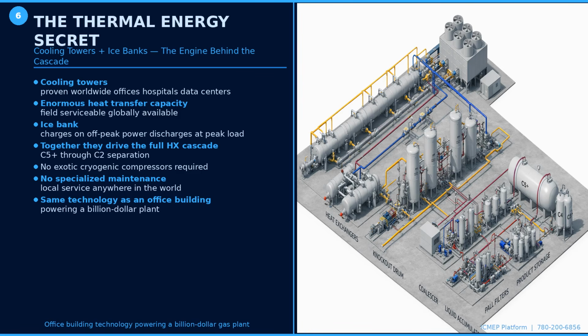Here is the engineering insight that changes everything. You might expect a system that separates hydrocarbons at temperatures down to -60 degrees Celsius to require massive, exotic cryogenic refrigeration machinery. It does not. Almost all of the thermal energy needed to drive the entire cascade comes from 2 of the most proven, widely available technologies on Earth: cooling towers and ice banks. Cooling towers are already installed all over the world, cooling large office buildings, hospitals, data centers, and factories. They are engineered for enormous rates of heat transfer. They are reliable, locally serviceable, and available on every continent.